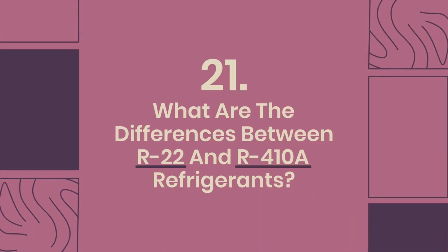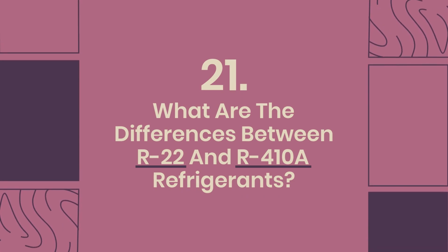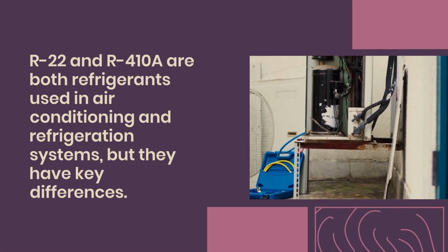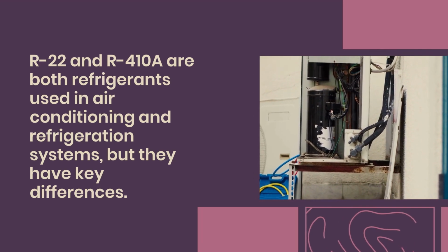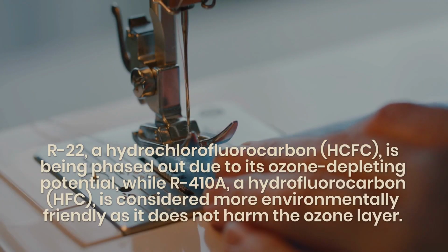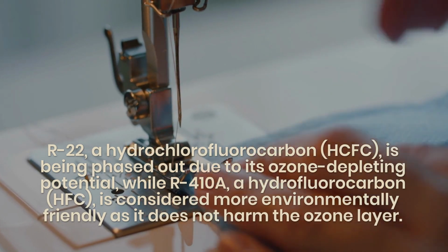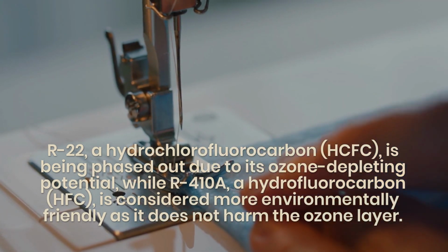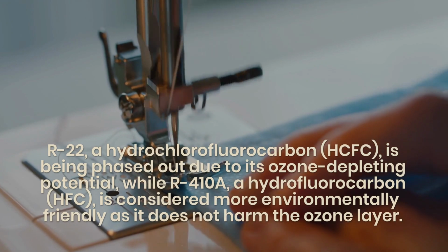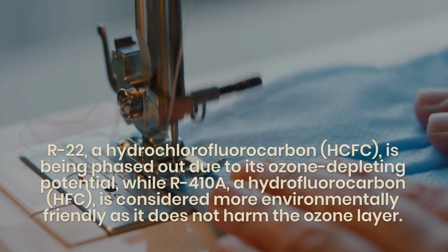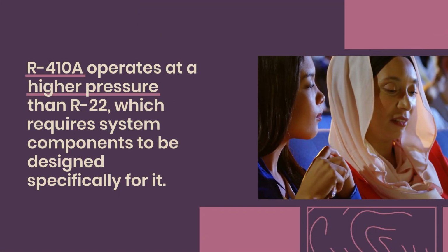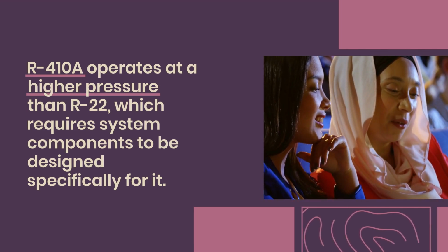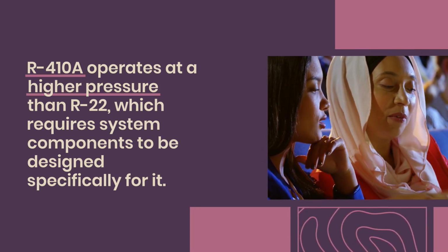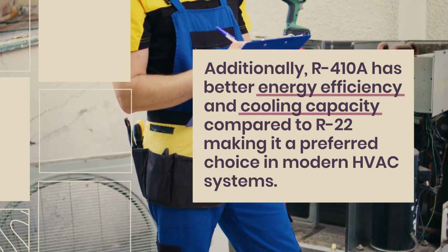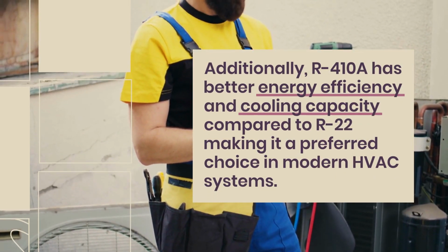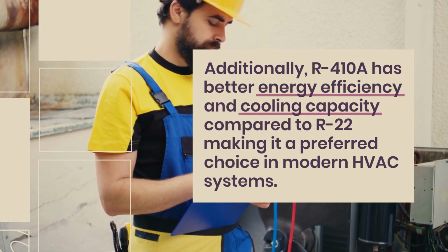21. What are the differences between R22 and R410A refrigerants? R22 and R410A are both refrigerants used in air conditioning and refrigeration systems, but they have key differences. R22, a hydrochlorofluorocarbon, HCFC, is being phased out due to its ozone-depleting potential, while R410A, a hydrofluorocarbon, HFC, is considered more environmentally friendly as it does not harm the ozone layer. R410A operates at a higher pressure than R22, which requires system components to be designed specifically for it. Additionally, R410A has better energy efficiency and cooling capacity compared to R22, making it a preferred choice in modern HVAC systems.